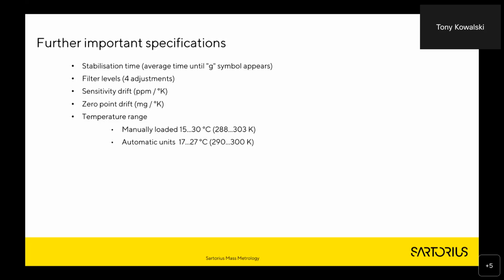So mostly people, when working in a mass calibration laboratory, don't take the first reading as G appears. G appears, which is the gram, or mg for milligram. Count a few seconds, maybe 5 seconds. Do that for every measurement and you get a better value.